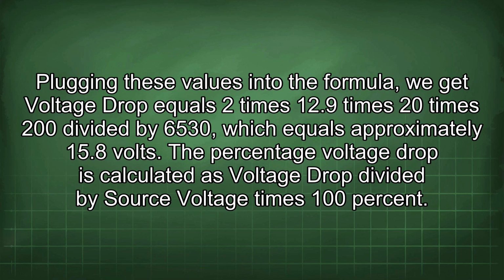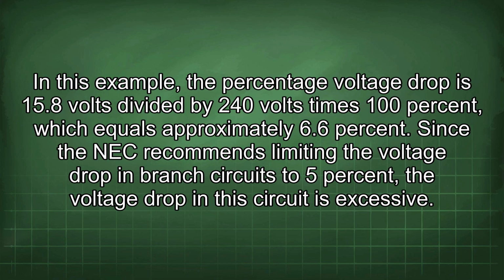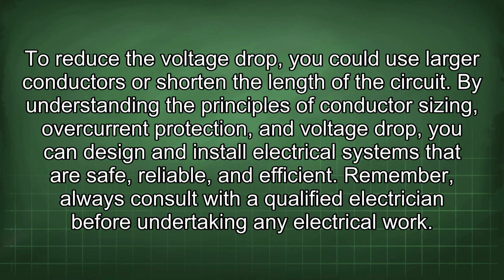The percentage voltage drop is calculated as voltage drop divided by source voltage times 100%. In this example, the percentage voltage drop is 15.8 volts divided by 240 volts times 100%, which equals approximately 6.6%. Since the NEC recommends limiting the voltage drop in branch circuits to 5%, the voltage drop in the circuit is excessive. To reduce the voltage drop, you could use larger conductors or shorten the length of the circuit.